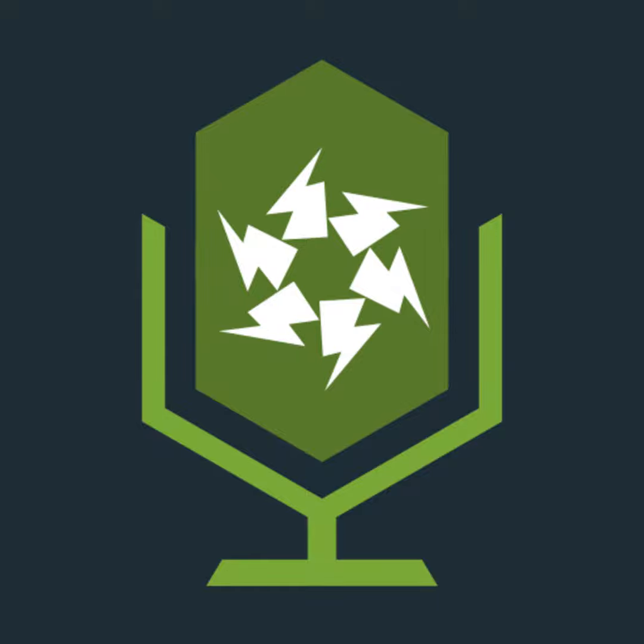So what we consider is the potential sources of this overvoltage. So we mentioned that if you had a lightning strike, it will go down to Earth, but then it could be induced. That voltage that goes down to Earth is looking for an Earth, and if you have lightning strike, let me just use this illustration quickly to show you this. If you have lightning strike an overhead line or a transformer, it's going to send this voltage down, and it's looking for an Earth. And whilst there'll be an Earth at the transmission end for obviously the network, here your Earth is locally sourced. So when lightning and voltage hit this, they're going to be going down to that Earth. Once this voltage has gone underground into the mass of Earth, it starts to lose energy, it starts to disperse, but it's seeking a better Earth, because ground is not a brilliant conductor for the voltage.